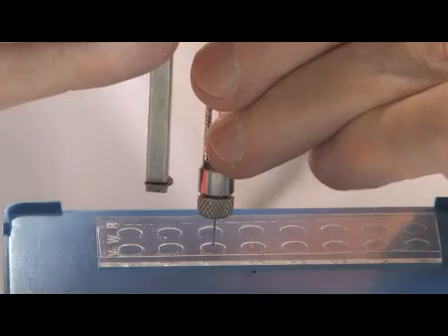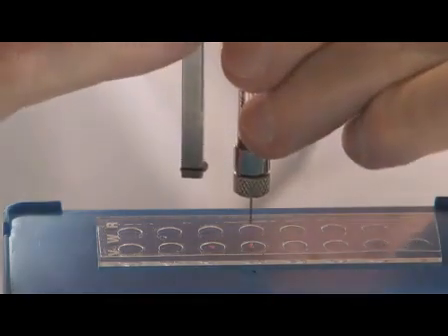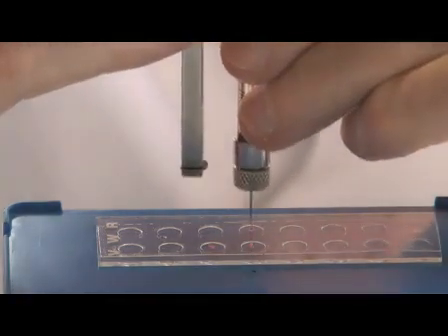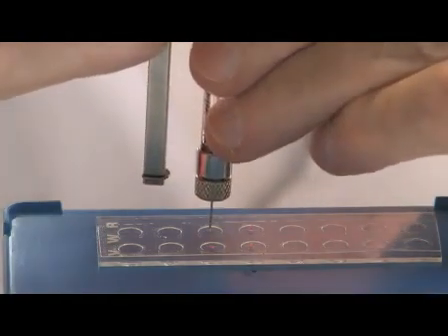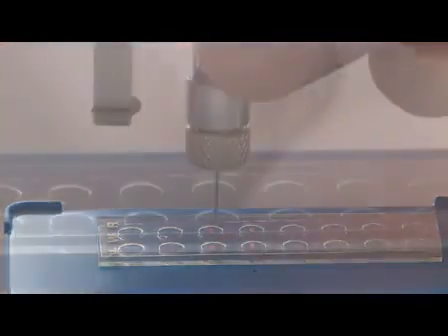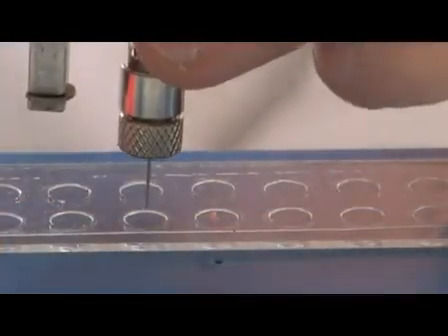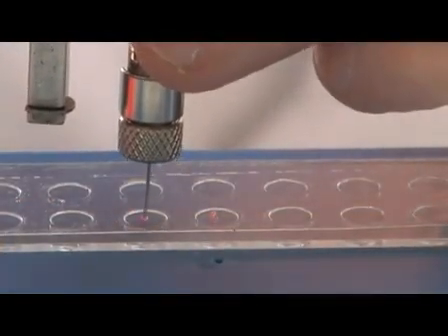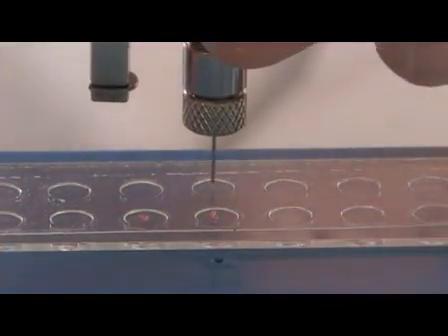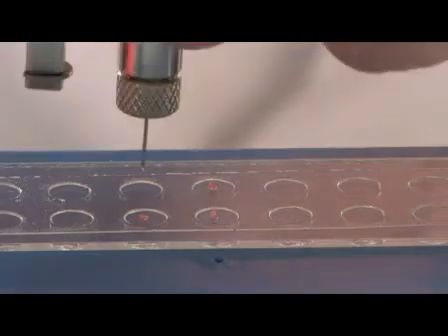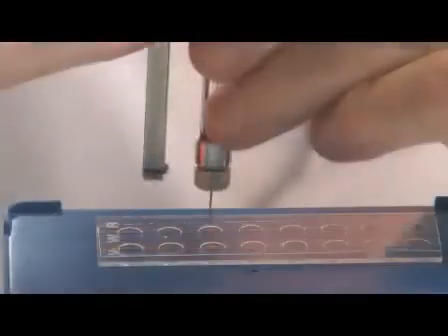The bolus volume is 200 nanoliters when the standard repeating dispenser is used with a 10 microliter syringe. The tip of the needle should be no more than a few hundred micrometers above the base of the well to ensure proper delivery. Reproducible delivery is easily achieved, it just takes a little practice.